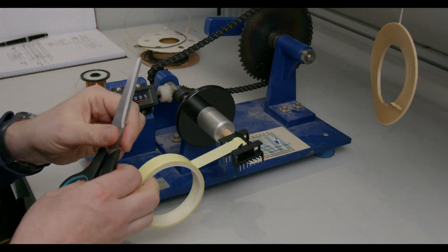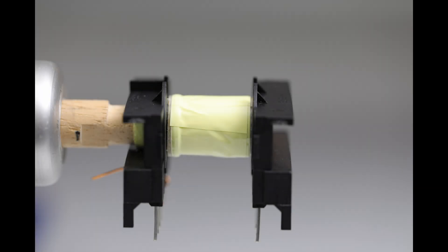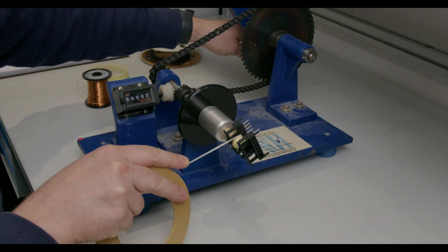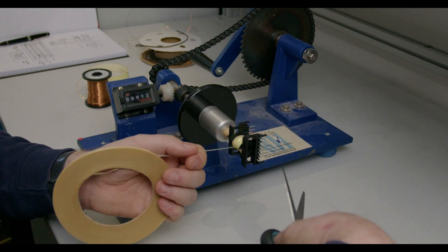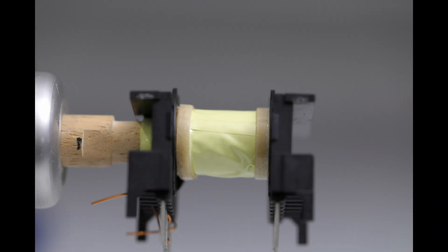We now wrap the winding with three layers of insulation tape and further margin tape on top of that at each side of the winding area. Note that for the actual windings we maintain the same winding direction with the start of the winding nominated as the dot end. This ensures we always have the correct winding polarity.